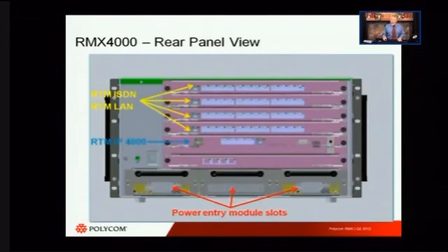In other words, I have 3 power cords in the back that you'll see on this next image. And those 3 power cords plug directly into the power supplies themselves. Okay, so you could actually have two of the power supplies coming off one grid, the other power supply coming off a different grid if you wanted to. That's certainly applicable, certainly valid in this situation.